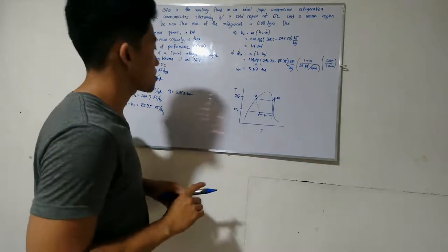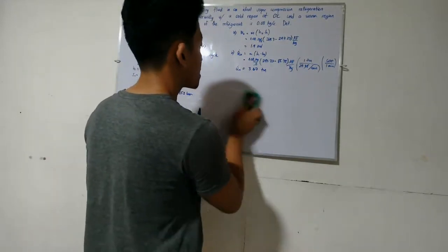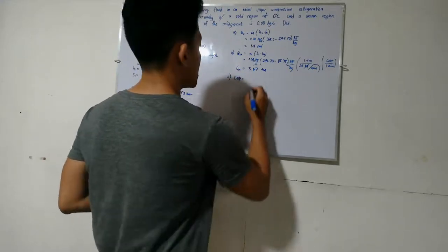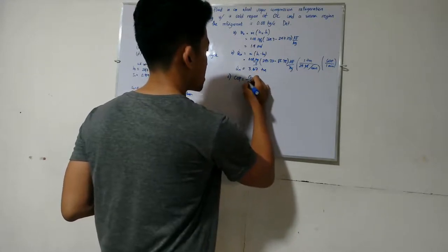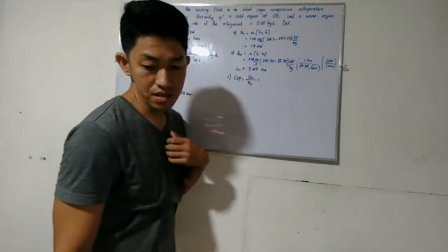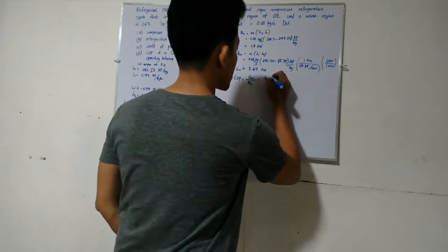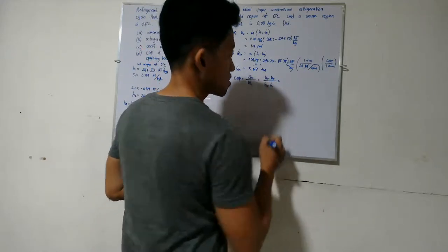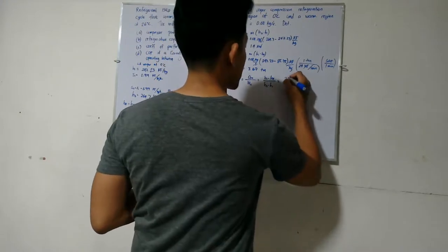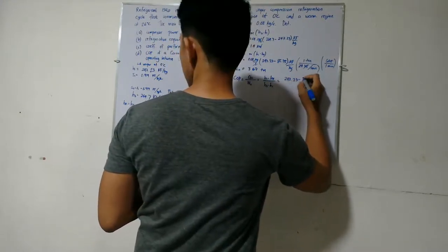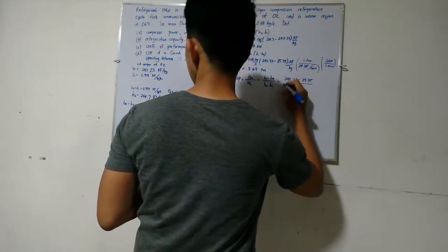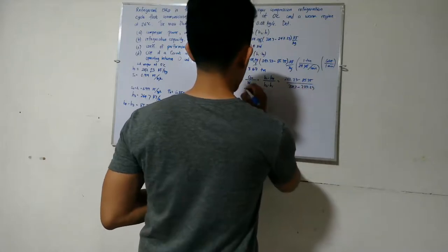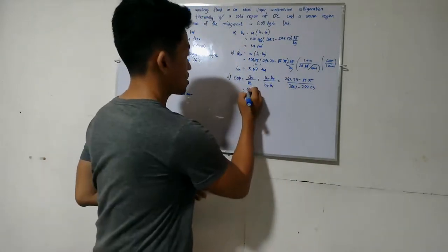For the coefficient of performance: beta = Q in / W compressor = (h1 − h4) / (h2 − h1) = (247.23 − 85.75) / (264.7 − 247.23) = 9.24.